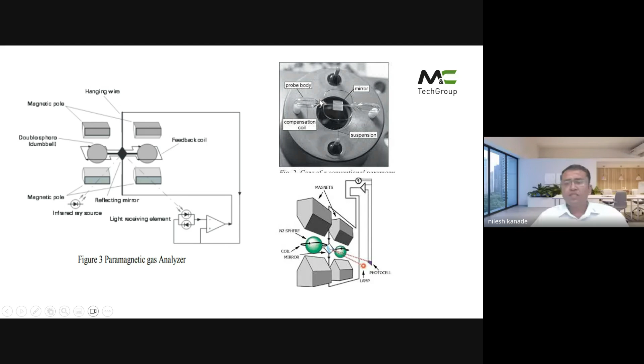The detector does not have heating parts. The important thing about this kind of analyzer is that there is no heating part. Because it works without heating, these sensors are suitable for measuring oxygen in flammable gases. Mostly these analyzers play the most important role in the process industry and oil and gas industries, where hazardous gas mixtures or emissions are produced. It is very small in size, easy to handle, and usable with a wide range of power supplies.